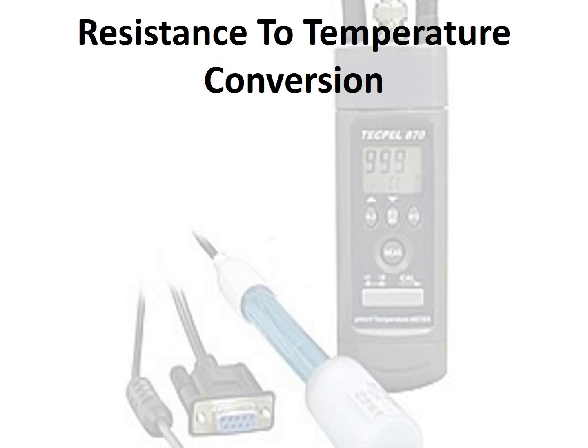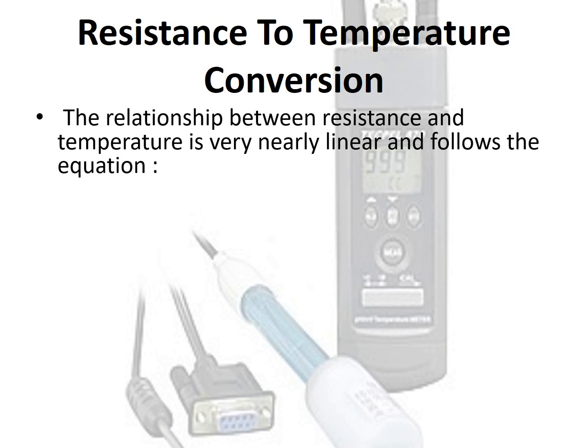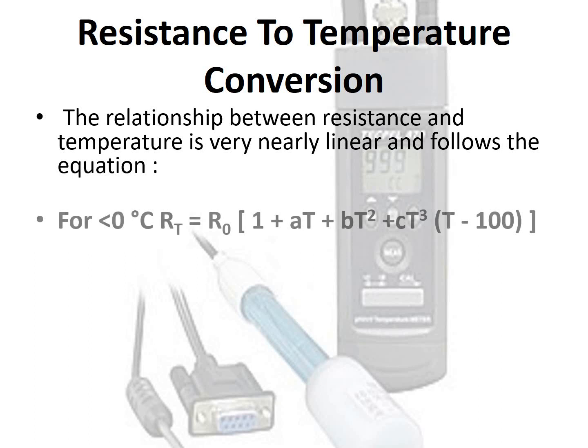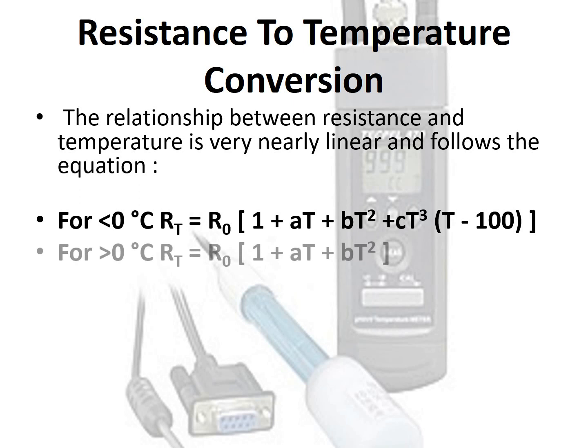The relationship between resistance and temperature is very nearly linear and follows the equation. For temperatures less than 0°C: RT = R0 × (1 + AT + BT² + CT³ × (T − 100)). For temperatures greater than 0°C: RT = R0 × (1 + AT + BT²).